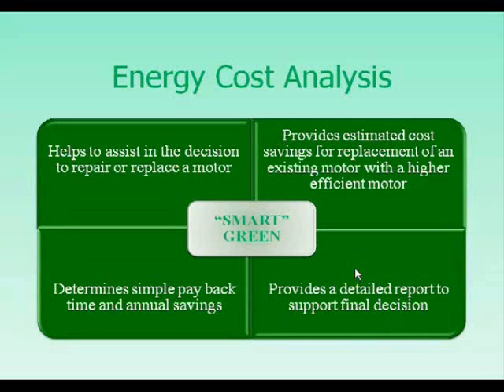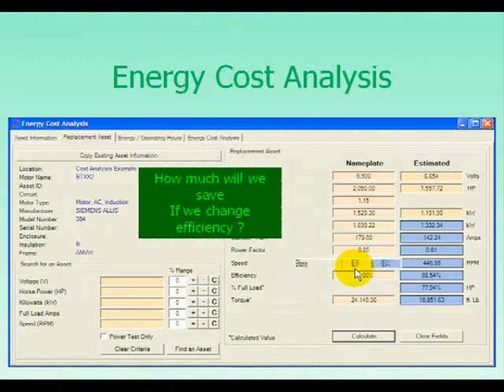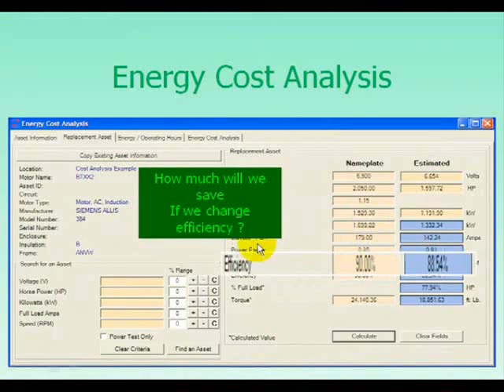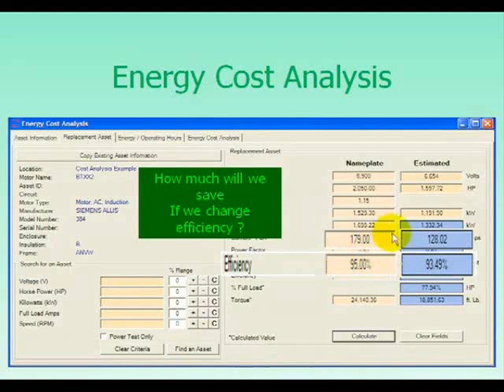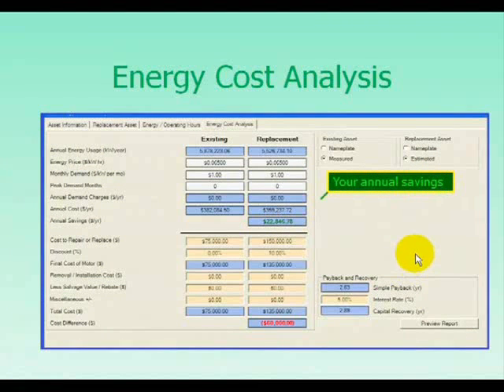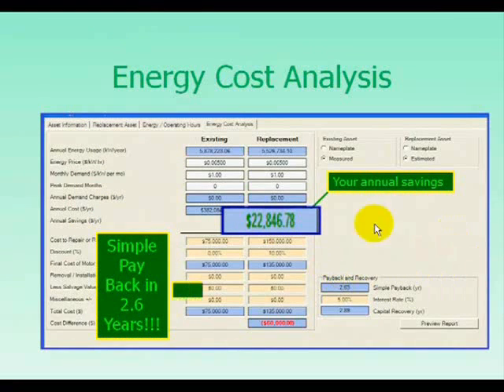So let's take a look at this software. We look at our energy analysis icon and up pops our energy analysis screen. Here, we want to look at and change the efficiency of this asset from 90% based on nameplate — with the estimated running efficiency at about 88% — and change that to a 95% efficient asset. Once we do this, we want to see what our annual savings are going to be. We've gone from 90 to 95 and we're estimating a 93% efficiency based on the condition that motor is running in. Our annual savings would amount to $22,846.78 in saved energy costs.